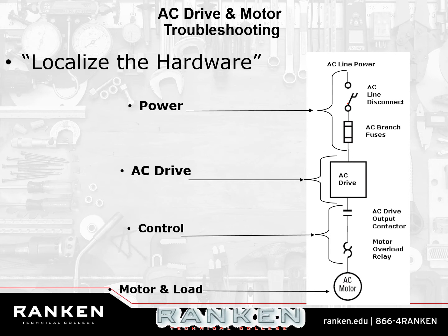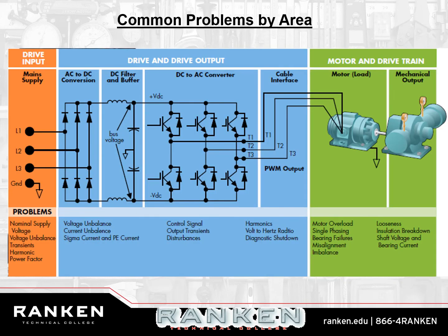This is a mechanical issue. Whatever, the coupling that attaches the motor to the pump is broken. Yeah, the reason the pump isn't pumping is because there's a coupling broke, or the shaft broke on the pump. Not my job. Sometimes it'll be your job, depending on where you go to work, but in bigger plants, they have a separate crew that fixes that.